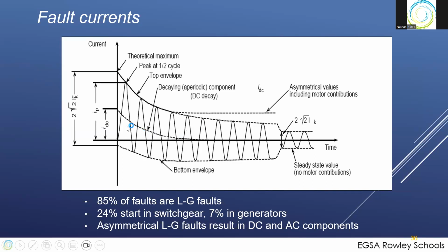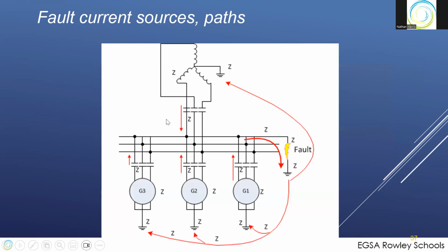And there's asymmetrical current. So when you get a fault, it jumps up to a high value and then decays with this DC component in here, L over R ratios or other. And this DC decay component is what actually can cause a source of induced or galvanic currents as well. It's important to have this galvanic isolation to prevent these from causing a problem.